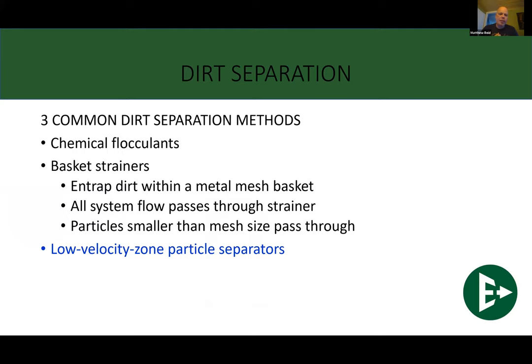There's three basic types. There is your chemical flocculants. What these do is they scavenge around looking for ferrous particles and dirt and whatnot, and creates it clumps them together. Then here's your basket strainers, aka the Y strainer, which I'm going to get to because I hate Y strainers with all my heart and soul. And I'll tell you why. It's not just a needless issue that I have with them. There's a reason. And then you get into the low velocity zone particle separators. But let's see what we got.